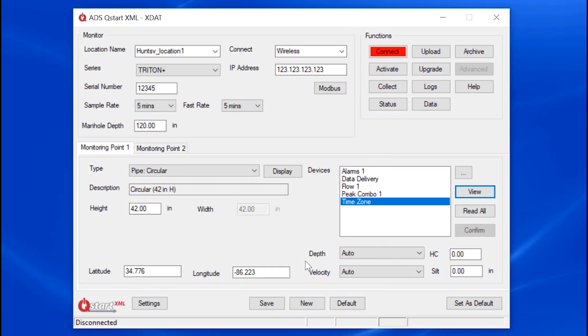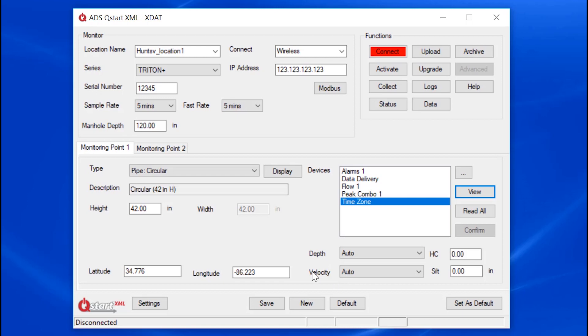Before we save all of our parameters for this monitor setup, I can choose to designate at the sensor level what is used for unit depth and velocity, the average velocity. Note that QSTART XML does not create a raw value for the peak and combo velocity sensors. It stores the entity velocity instead. The default setting of Auto allows the firmware to choose the best choice for unit depth and velocity.